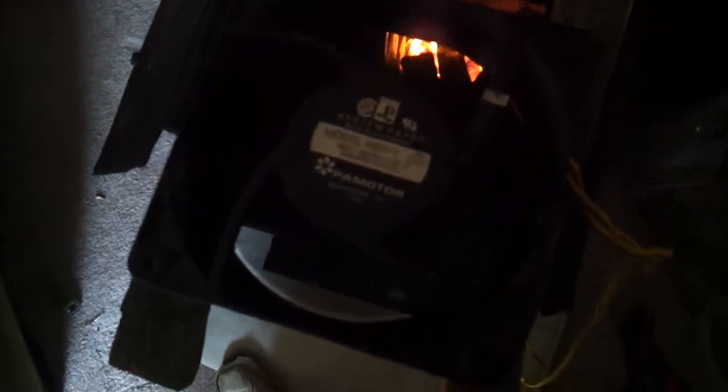I'm having a real issue trying to get a good draft going, especially the past couple of days. We've had a north wind and that's been putting positive pressure on the side of the house. I've implemented a fan for now to try to basically power vent this thing. I also added this diverter plate and that goes all the way down to the bottom — there's a bit of a gap at the bottom, probably about a half to three-quarters of an inch.